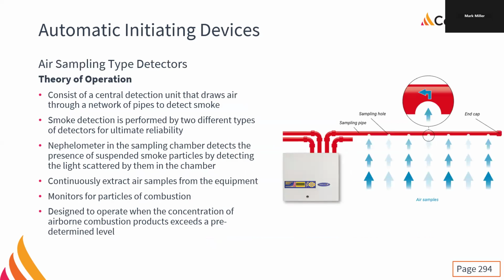We also install our own holes, right? You get to drill the holes in yourself, and you get instructions on exactly what size of holes and how far apart and all that. And the more holes you have, the higher the fan speed you need to have, and all that stuff for configuration. One of the issues with the elevator shaft, a one-car elevator shaft really only needs one sampling hole, and so it's really susceptible to pressure changes and to clogs.